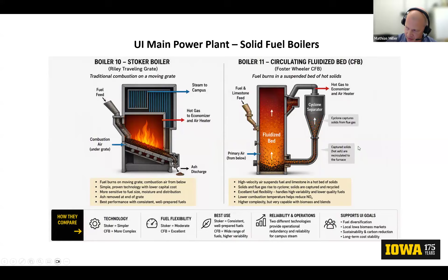On the other side of the spectrum, we have what you'll hear me call a CFB, a circulating fluidized bed boiler. What we're dealing with here is essentially a suspended fireball, suspended by air, and this thing can burn all kinds of material. The key with this unit and others like it is it requires a certain amount of ash to circulate around in the boiler to carry the heat for heat transfer, and we'll get to that a little more in a bit. So, two different boiler technologies, two different solid fuel boilers in use at the main power plant.